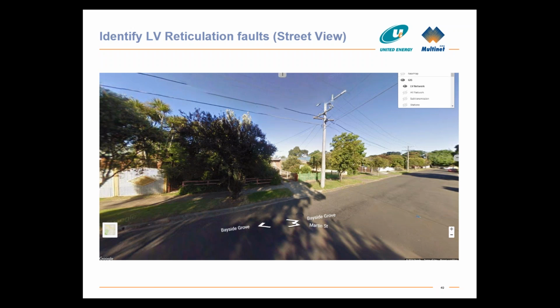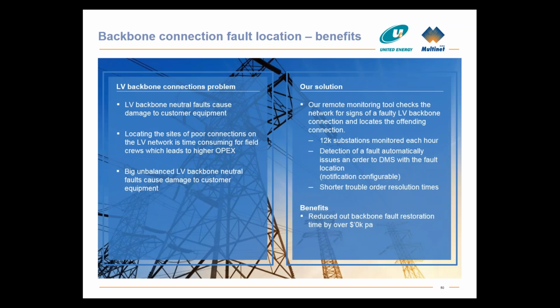Time and again, we just have to go there and replace the connections between the two cross arms. It's a jumper, a bad connection on the jumper between the cross arms, and about 80% of the time it's a neutral jumper causing all these issues. We go fix that, and the problem is gone.